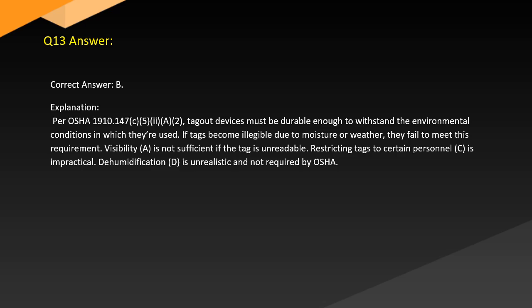Answer. Correct answer B. Explanation. Per OSHA 1910.147(c), tagout devices must be durable enough to withstand the environmental conditions in which they're used. If tags become illegible due to moisture or weather, they fail to meet this requirement. Visibility, A, is not sufficient if the tag is unreadable. Restricting tags to certain personnel, C, is impractical. Dehumidification, D, is unrealistic and not required by OSHA.